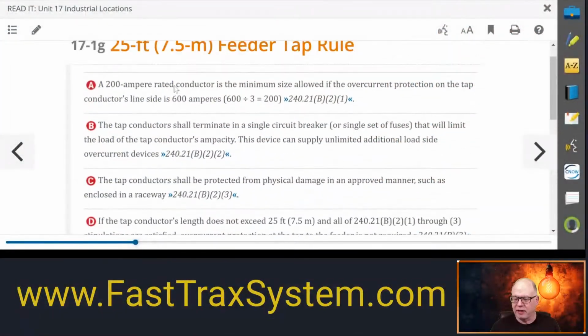It's a magical dance to get used to everything. So one of the things that people get confused with is sizing the protection for the transformer, and they forget that there are conductor rules that are totally separate that you have to follow. Okay. All right. So let's go to, real quick, see if we can't cover the 25-foot secondary.